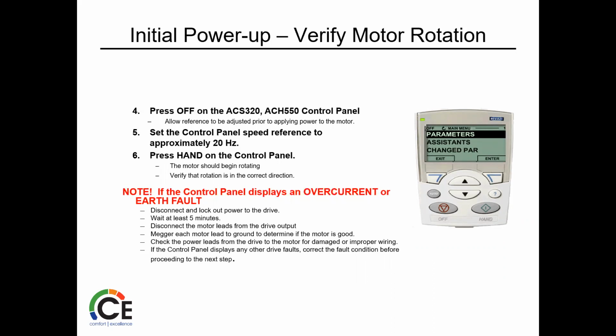So they're talking here about verifying rotation. Hand in this, if you see down on the bottom right, that's basically your manual operation. So that's the first thing you want to try, right? Hit the hand mode, see if the motor runs. If it doesn't, now we've got to go into some other things and see what's going on. But again, without this control, you can't even do that. So you're basically just running the wires right to the motor and letting the thing run.